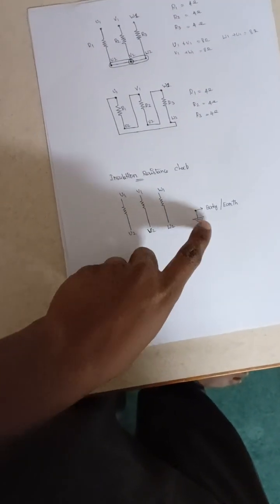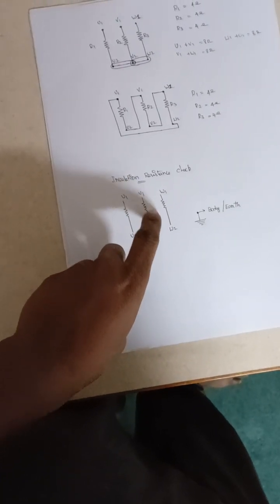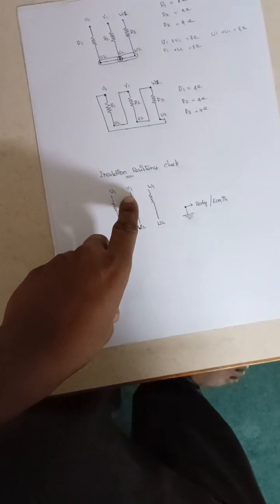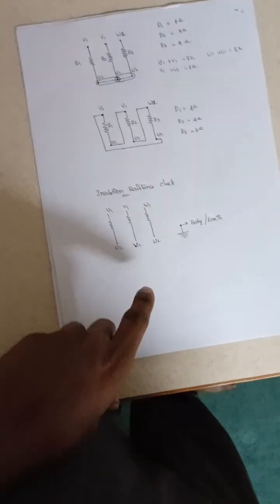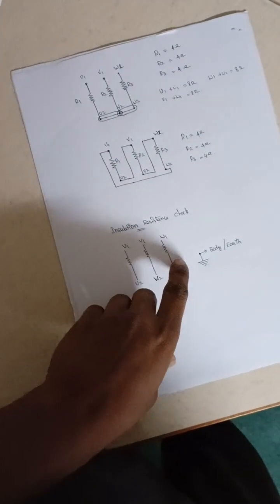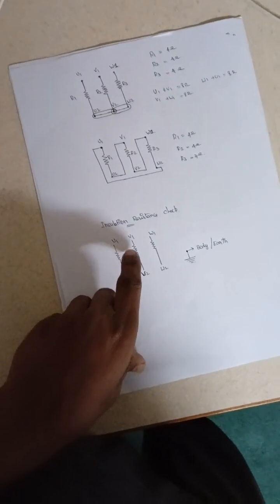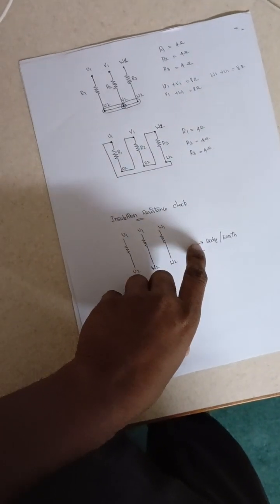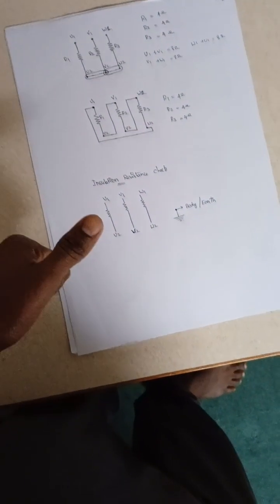Between the windings, we will take the earth cable of the Megger and put it on any one of the windings, and we will check the other winding. By this we can find out the windings are not shorted. While measuring the resistance between the winding and the earth, we can find out there is no short to the body. Thank you. Do well.